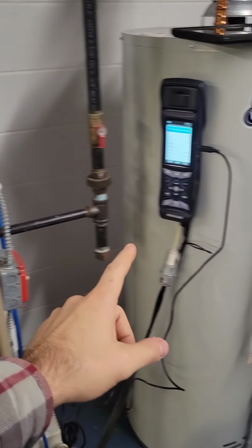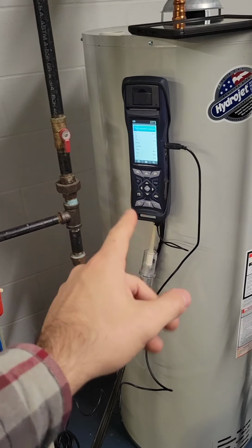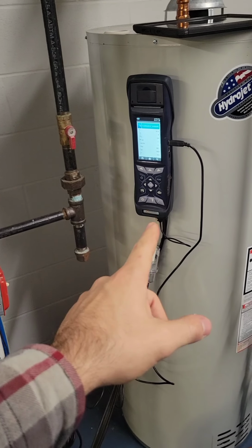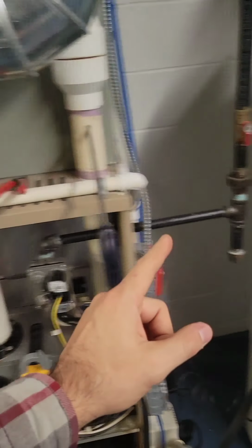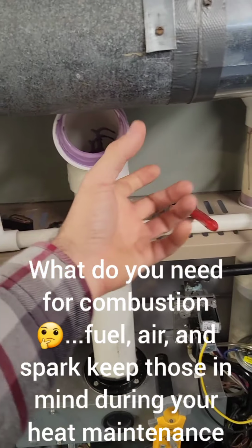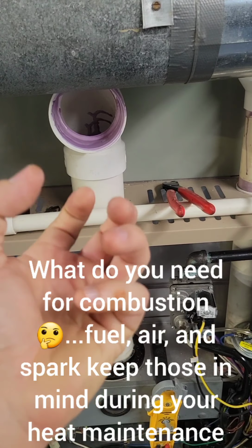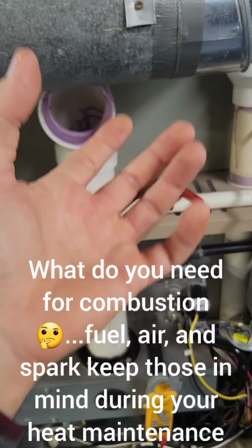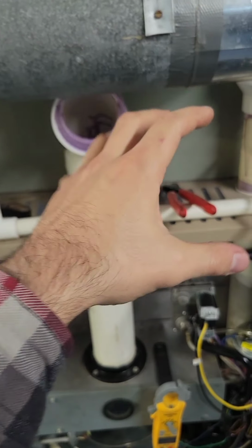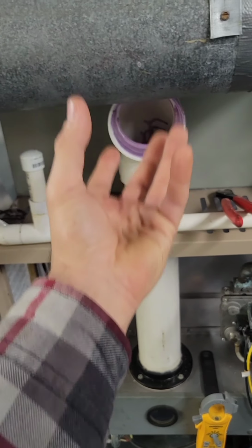And now typically I will hook up a secondary K-type thermocouple in there and attach it to the intake to make sure that we're reading the air from the outside. So obviously the air from the inside is a lot different than the air from the outside. It's colder outside, right? So your delta is going to be a little bit different.